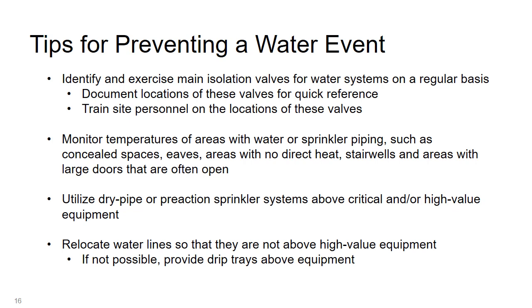This may not always be possible as a result of hospitals having critical needs for water supplies, so fully closing domestic water valves may not be possible. This should be coordinated for an idle period when safe to do so. Second point here touches on monitoring temperatures. This may include opening interior doors to stairwells to ensure that there's sufficient heat present in the stairwells to minimize potential for freeze-ups.